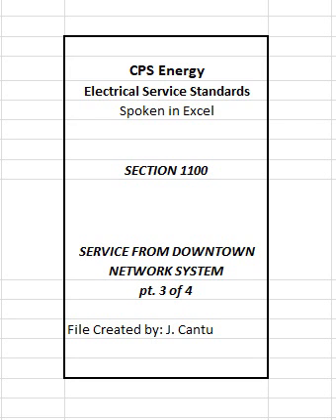2. The location for fuse pads shall be on the transformer vault or room wall as specified by CPS Energy. 3. Customer shall advise CPS Energy of bus bar width or cable size and quantity to connect to fuse pads, plus any other details related to connections on fuse pads. CPS Energy will not allow bus bars having a width less than 4 inches to be connected on its fuse pads.